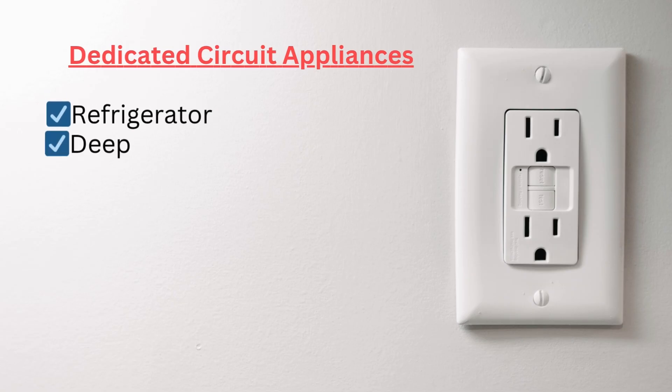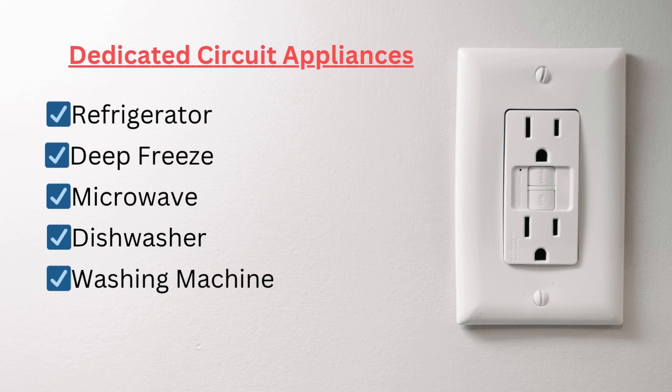A few different appliances that you really shouldn't incorporate into any circuit with more than one outlet: a refrigerator, deep freeze, microwave, dishwasher, washing machine, or electric fireplace. Some of these appliances either draw a lot of amperage on their own or it's required by code to have them on their own circuit.